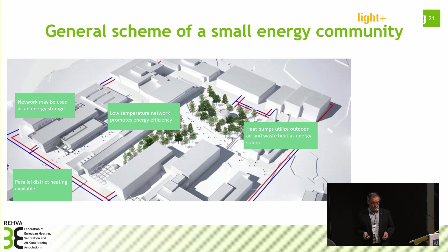So we have this low temperature heating network that is supplying 45 degree water in the buildings, where there is also another parallel heat exchanger for district heating. There is one exception: one new building part that is built for the low temperature heating system, so it does not need district heating for space heating and ventilation, because the whole system is designed for low temperature. But all the other buildings are old buildings, so they have high temperature demand. So we need to have parallel district heating there.